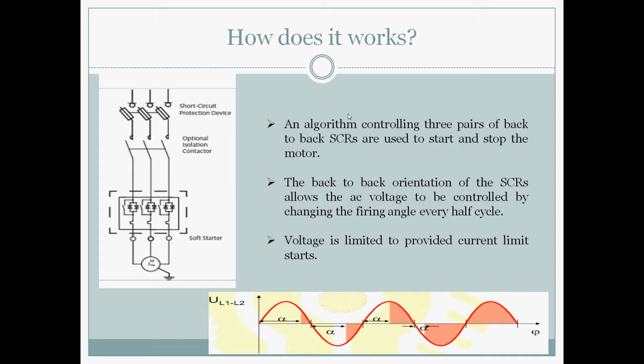And how does it work? An algorithm is controlling 3 pairs of back-to-back SCR thyristors used to start and stop the motor. The back-to-back orientation of the SCRs allows the AC voltage to be controlled by changing the firing angle of the half cycle. So the firing angle you can see from here. Every half cycle the firing angle is increasing. For the first half cycle the firing angle is that. The second half cycle firing angle increases a bit and slowly it is increasing. In the SCR connection, thyristor control, there are 6 back-to-back thyristors. It is controlling the firing angle.